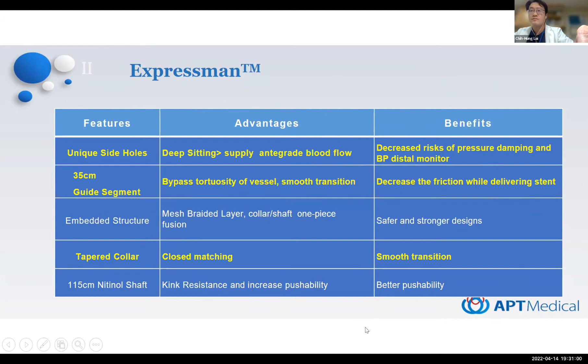The taper collars can have a good match, smooth transitions. But as just mentioned by our moderators, they have some special taper designs. This is a 6-French guiding catheter compatible Expressman. They have a 5-French outer diameter, but this is a taper design. They have a 10 centimeter, much smaller distal tip, around 4-French outer diameter. So it tapers from 5 to 4 in the distal 10 centimeters.